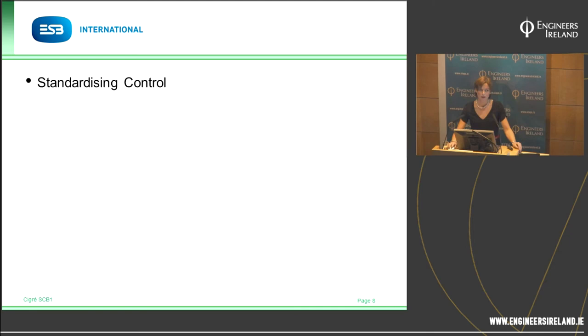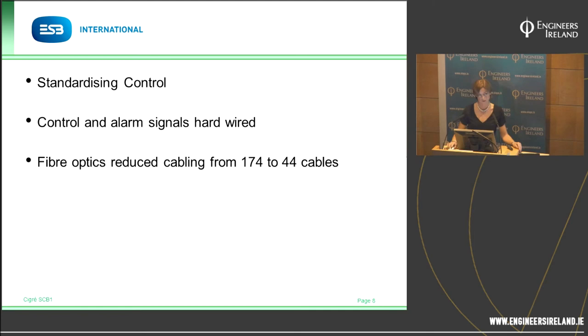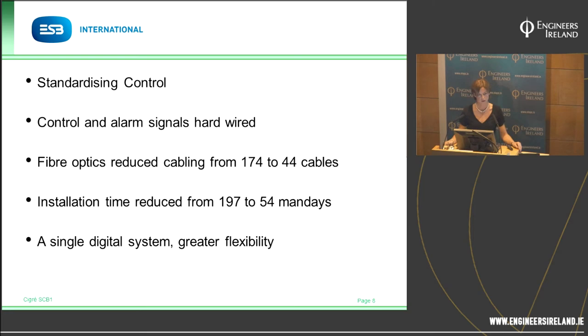We looked at standardising control. So traditionally, all the control and alarm signals from the switchgear and the relays were hardwired back to the control room. We reviewed this and decided to implement a digital system. The effect of this was that the number of cables used was reduced dramatically, which of course reduced installation time. And a single digital system had much greater flexibility, and it also replaced quite a number of large standalone pieces of hardware.